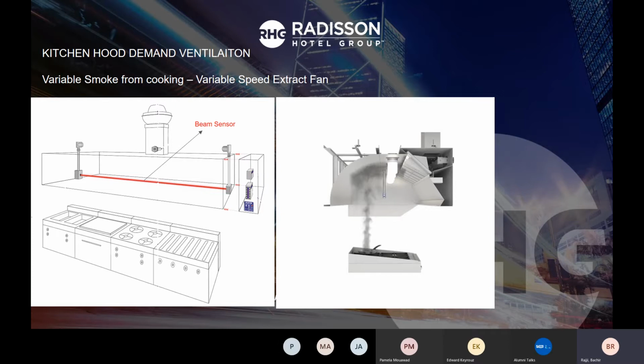So all this data can be collected on the BMS, which means the amps consumed by the motor, the rotation of the motor, the RPM, the beam sensor, and the concentration. We have what we call a sensitivity. We can also measure the sensitivity of the receiver. Let's say this one is sending, I don't know, 1,000 infrared beams, and the receiver is only receiving 500, which means the 50% cut is due to the smoke. They can convert these beams between the sender and the receiver into values on the software, so you can also measure the intensity of the beam sensor. You can measure the VFD, the speed of the VFD of the motor. We can measure the volts on the motor. You have all the flexibility to measure all the field devices and the control.